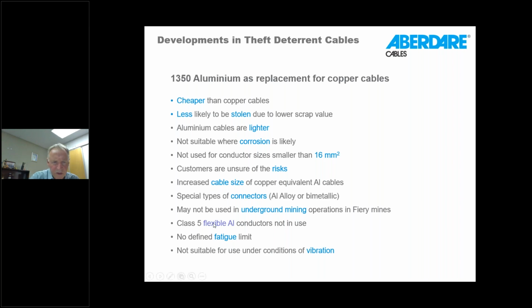If you're using hard-drawn aluminium, it is definitely a problem, because any little nick or stress raiser on the surface of the wire will cause early breakage. So hard-drawn aluminium, we all know from aluminium wire armouring, can break very easily. But when you have annealed aluminium, and particularly the alloys of the 8000 series, that is not the case. So 1350 is not suitable for use under conditions of vibration due to this fact.